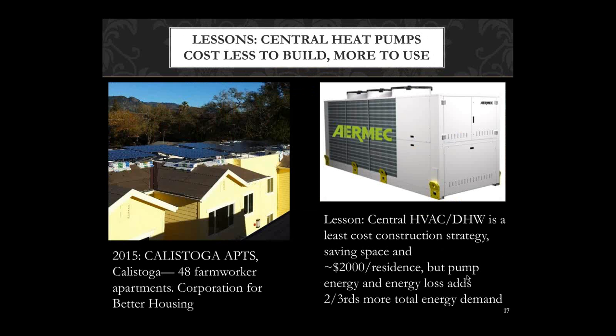Want to go into this in a little more detail? This is a different central system. This is an apartment complex in Calistoga for farm workers. We did save about $2,000 per residence on construction cost, but we've found, and this is true in other studies too, that it takes about 2/3 more energy demand to operate it this way, because at least 1/3 of the energy is lost to the environment as it circulates around. It's not like that with a small system for your house. You get pretty much all the energy delivered from a hot water tank or an HVAC system. But when you recirculate it around a big apartment building, or underneath the ground in the case of these three buildings, you're using a lot of energy to heat the environment that isn't your conditioned space.